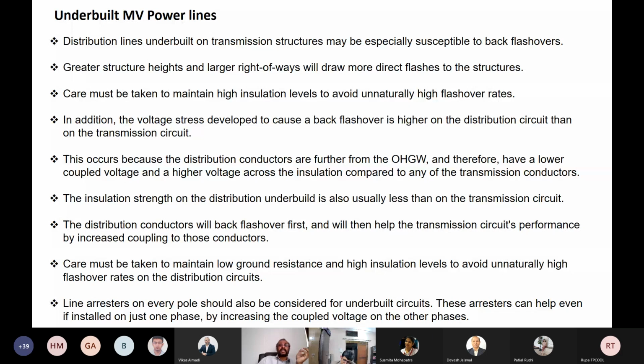Then in addition, the voltage stress developed to cause a backflashover is higher on the distribution circuit than on the transmission circuit. This occurs because the distribution conductors are further from the OHGW. I think I explained these things. Finally, what I want to emphasize is that in this case, you have to pay extra attention to the protection of transformers than in the case of standalone or isolated MV distribution lines.